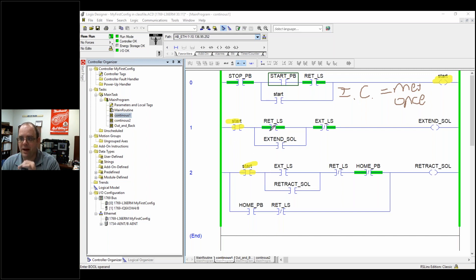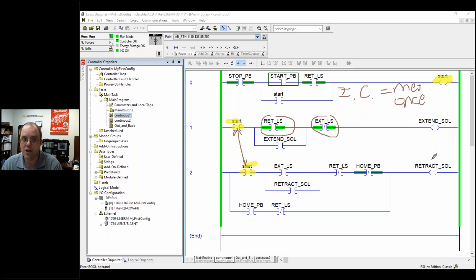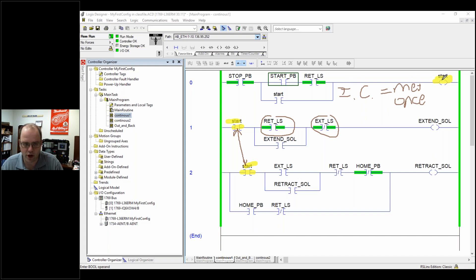This start condition bit will allow me to say: once initial conditions have been met once, do a cycle and keep repeating it. So I see 'initial conditions met once,' and once those are met, I keep power in my cycle. Notice I have my limit switch retracted — it's not going because it's not started yet. The benefit is that when I hit stop, the start bit will drop out and stop anything that's going on. Think of it like paying with a hundred dollar bill instead of a hundred pennies — I'm saying all of this equals start conditions, and once that's met, it stays on through the seal-in.